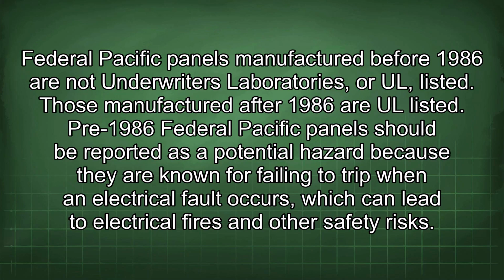Federal Pacific panels manufactured before 1986 are not Underwriters Laboratories, or UL, listed. Those manufactured after 1986 are UL listed. Pre-1986 Federal Pacific panels should be reported as a potential hazard because they are known for failing to trip when an electrical fault occurs, which can lead to electrical fires and other safety risks.